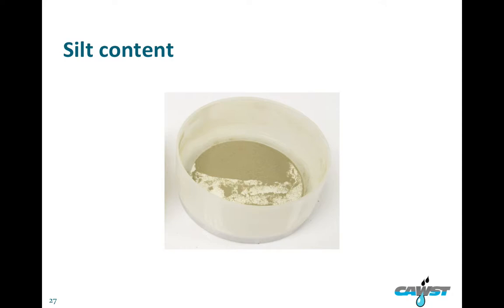One reason is that the sand preparation, especially the washing, is going to kill you if you have too much silt. Preparing filter sand is never easy, but from personal experience, when there's too much silt, it can be a horrible, horrible experience. The manual describes washing the sand 3 or 4 times and testing to see if that's enough. With a high silt sand, you can sometimes be washing your sand 20 times, and you might still need to wash it more. Once you've washed the silt away, if it was a big portion of your sand, your sieve analysis results will be different. The sieve analysis you did at the quarry will no longer be very accurate. Your sand might be quite a bit larger than you thought it was.